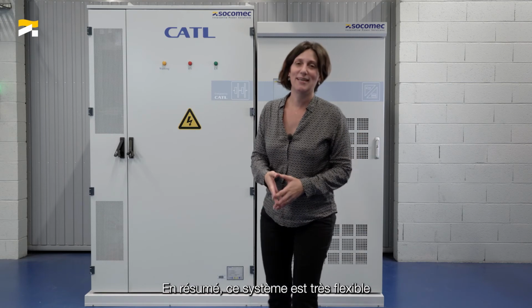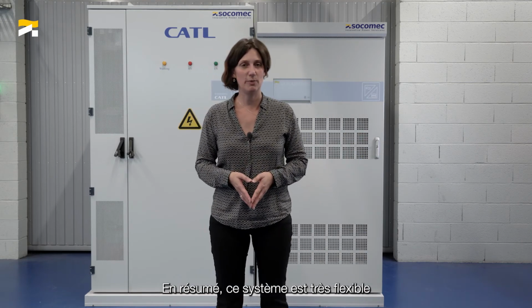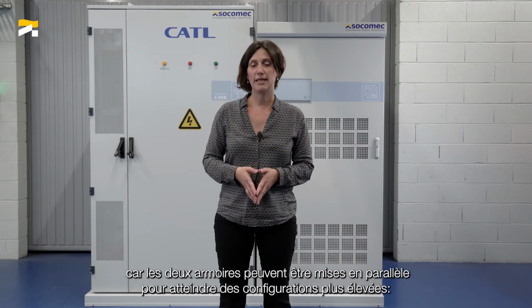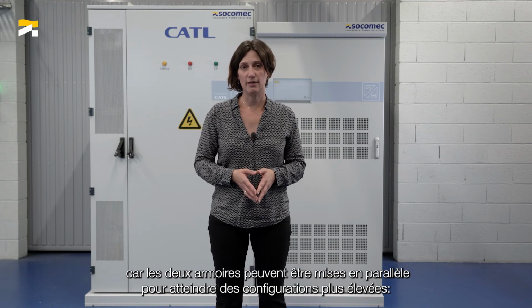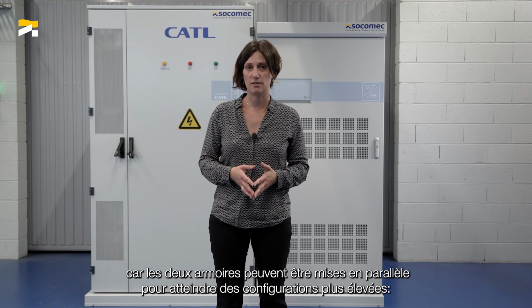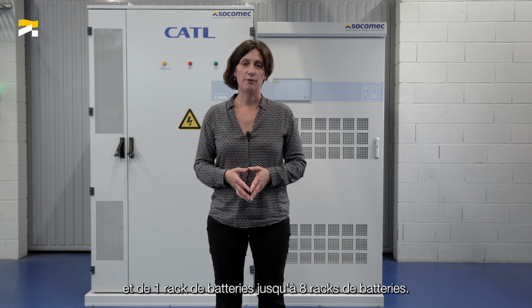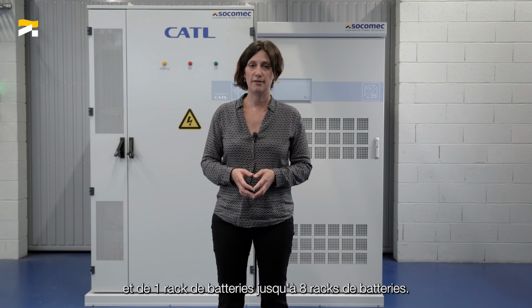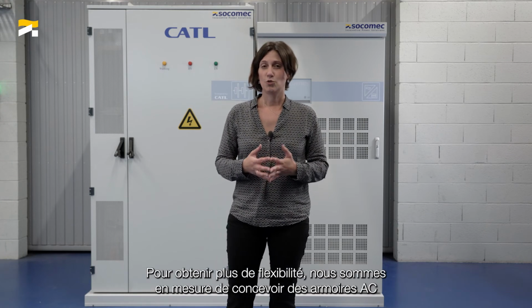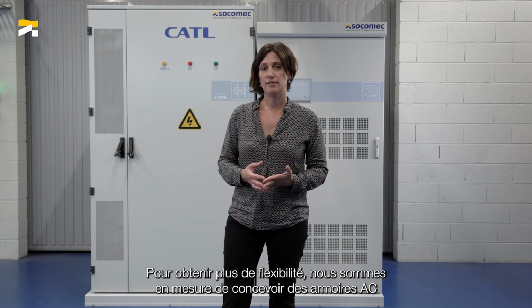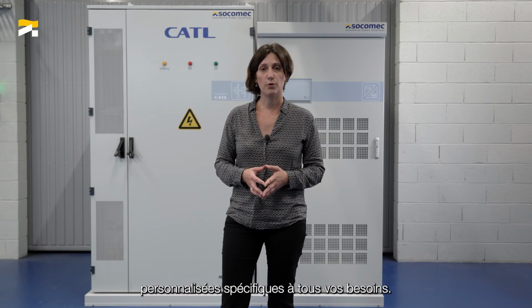To summarize, this system is highly flexible because we have two main cabinets that can be put in parallel to reach higher configurations. So from 50 to 850 kVA and from 1 battery rack up to 8 battery racks. To get some more flexibility, we are also in a position to design specific customized AC cabinets for all your needs.